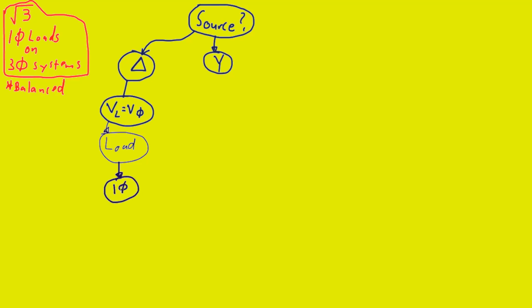Does the current given in the particular problem match the way the load is connected? And this is where the root 3 is really going to come into play, because what we're really looking to answer is just what I wrote there. Is the current that was provided to you by the problem really the current you need for your final calculation?